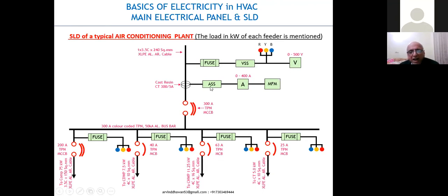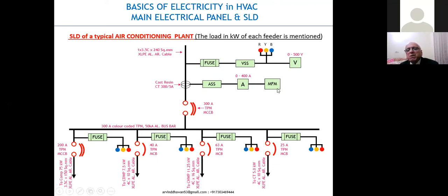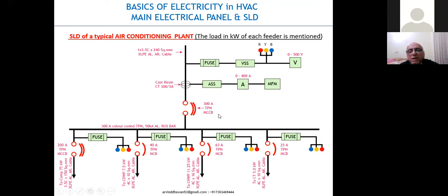ASS: A for ampere, S for selector, S for switch. MFM: M for multi, F for function, M for meter — the multi-function meter. It can read energy, frequency, and power factor. Then we come to the main switch: 300A means 300 amperes can be carried by this switch. TPN: T for triple, P for pole, N for neutral — meaning there will be three conductors plus one neutral, so four connections total in this switch. The conductors are color-coded red, yellow, blue, with neutral identified as black.